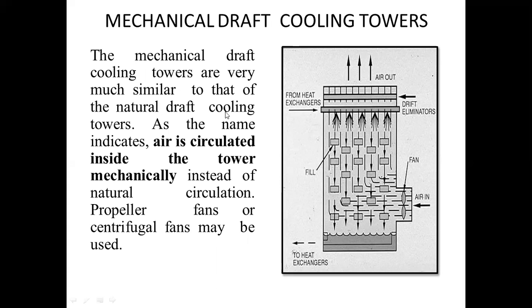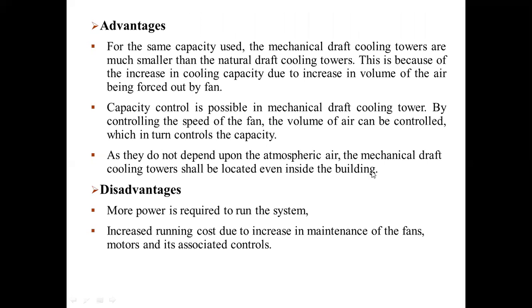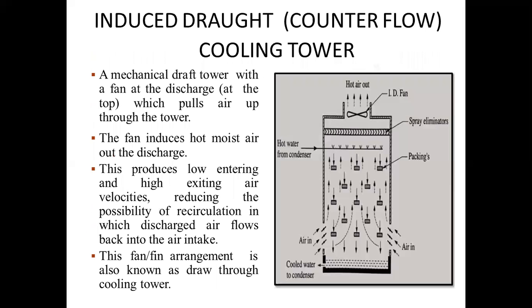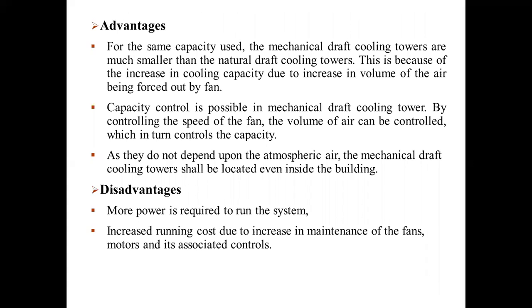Mechanical draft cooling towers are very similar to natural draft cooling towers, but here air is circulated inside the tower mechanically instead of by natural circulation. Propeller fans or centrifugal fans may be used. You can say in this case we are using a fan which supplies the air. It can be forced draft, induced draft, or balanced draft.